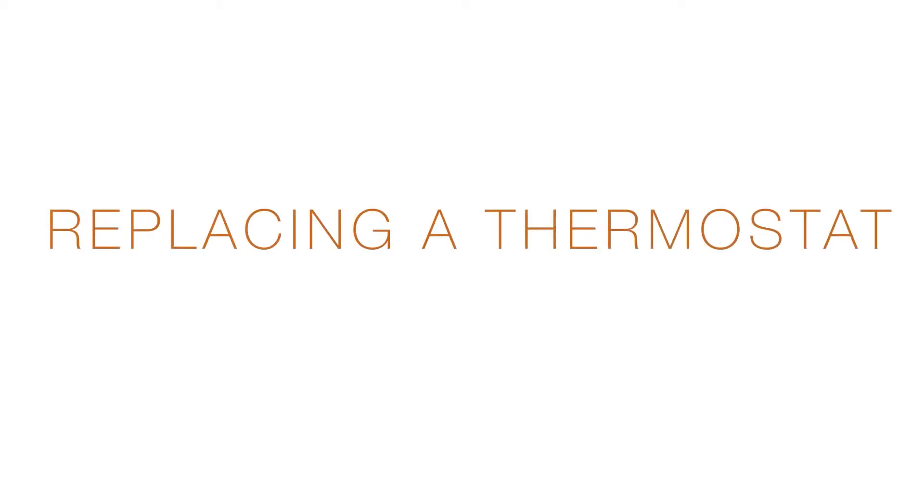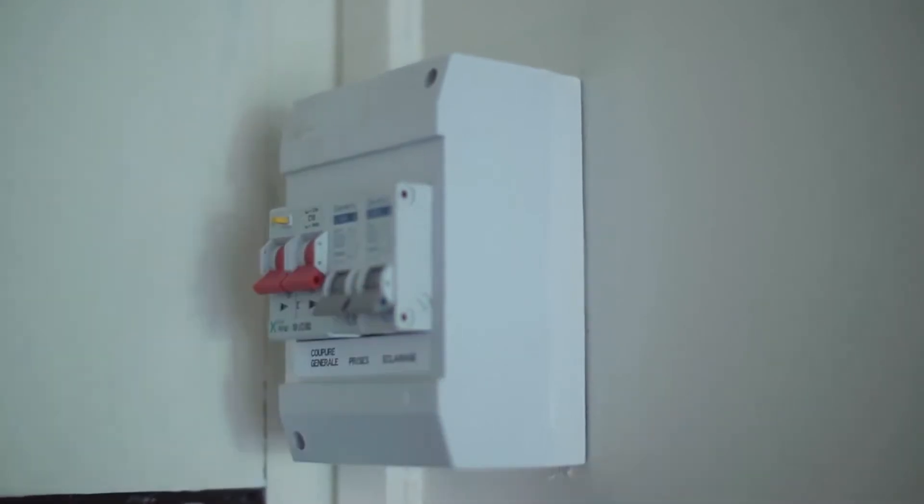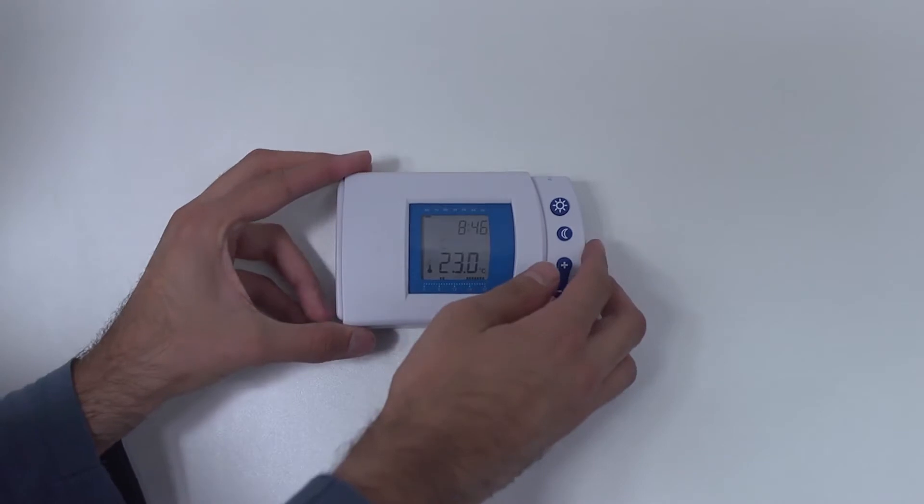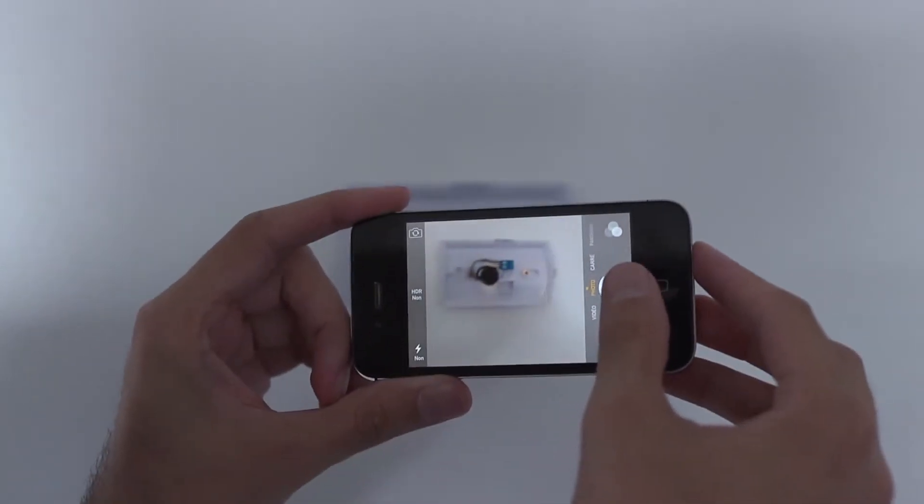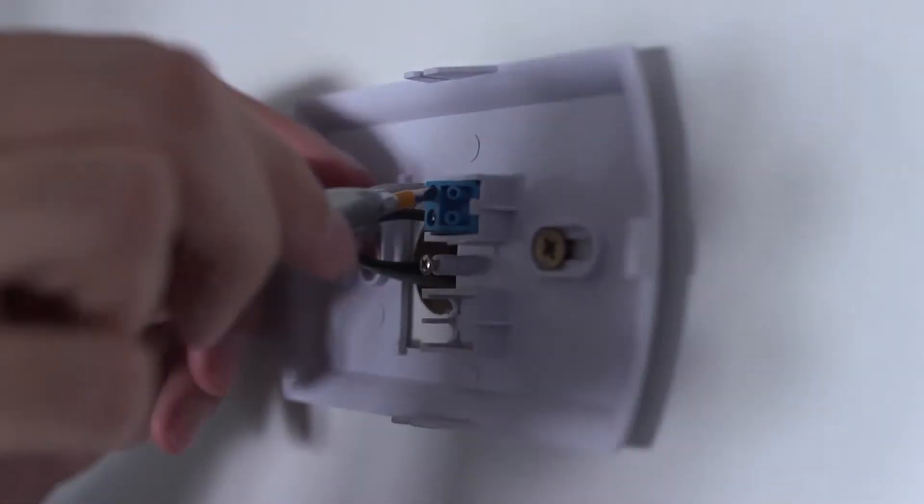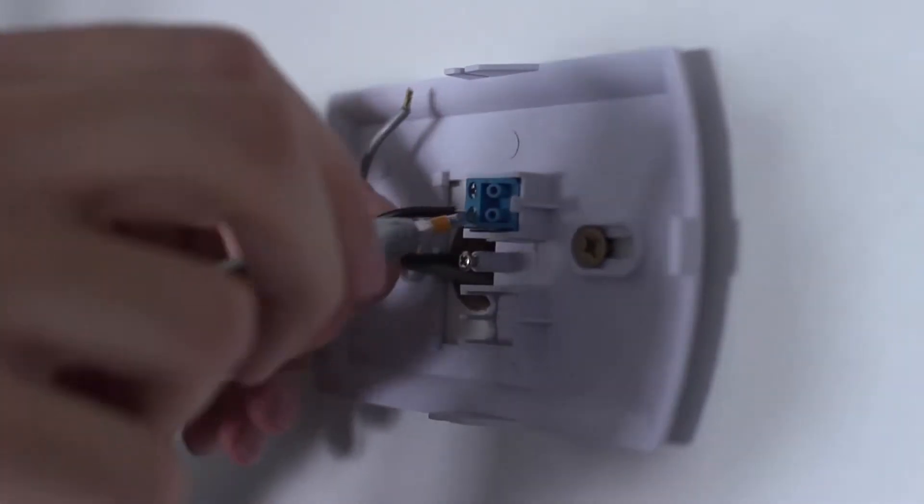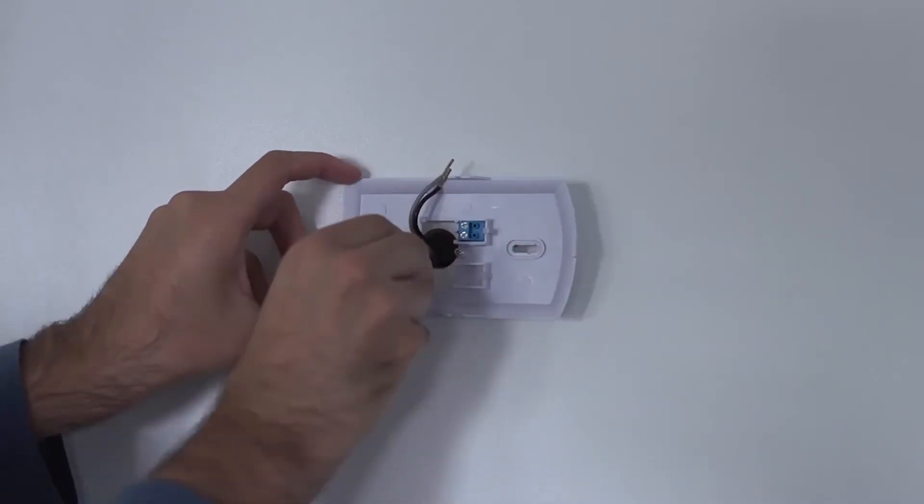Replace the thermostat. Before beginning installation, don't forget to turn off the power. Remove the cover of your old thermostat. Take a picture of the wires as they are. This will be a good reference to have if you have questions in the future. Unplug the control wires from the boiler with a screwdriver. Remove the old mounting plate from the wall.